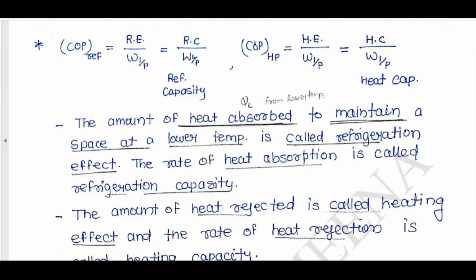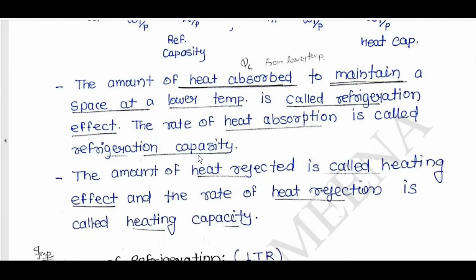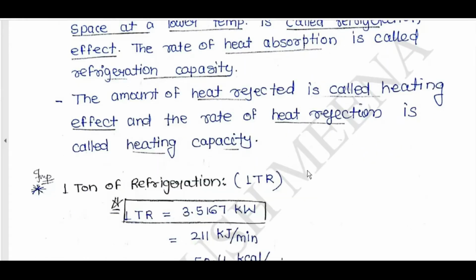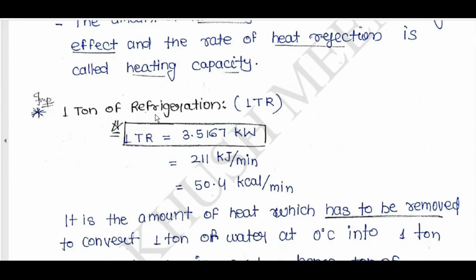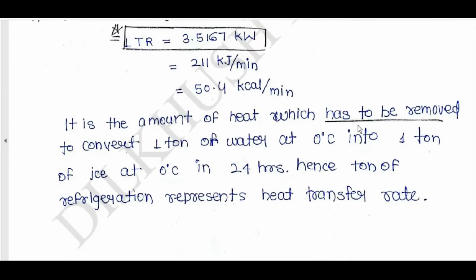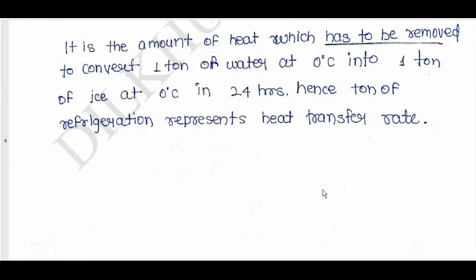The amount of heat absorbed to maintain a space at lower temperature is called refrigeration effect. The rate of heat absorption is called refrigeration capacity. The amount of heat rejected is called heating effect, and the rate of heat rejection is called heating capacity. 1 ton of refrigeration, 1 TR, is equal to 3.5 kilowatt, is equal to 211 kilojoule per minute, is equal to 50.4 kilocalorie per minute. It is the amount of heat which has to be removed to convert 1 ton of water at 0 degrees centigrade into 1 ton of ice at 0 degrees centigrade in 24 hours. Hence 1 ton of refrigeration represents a heat transfer rate.